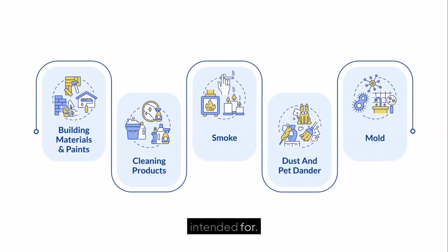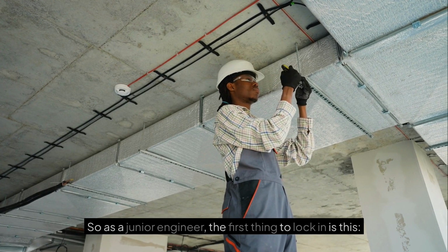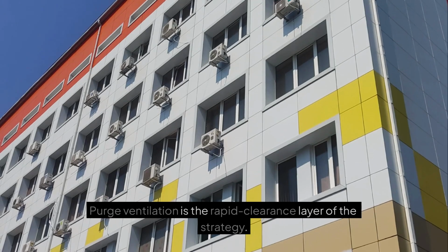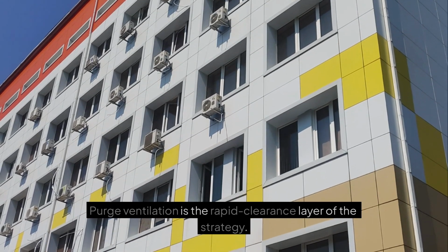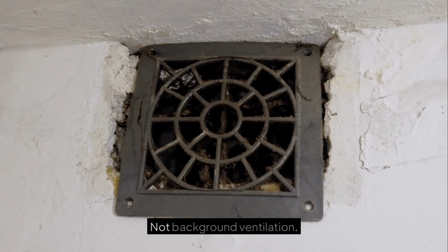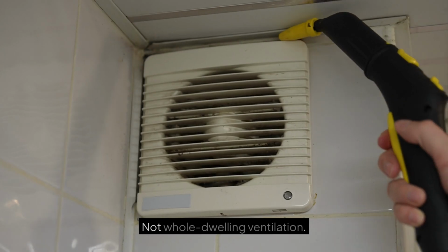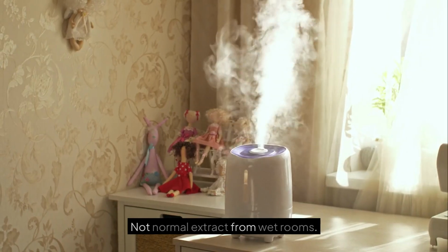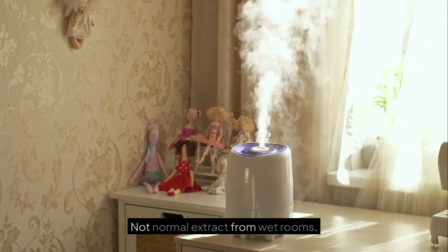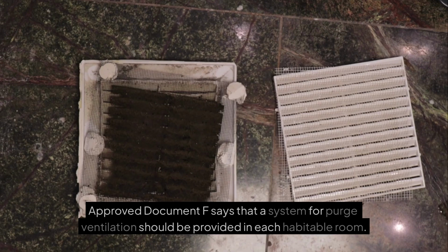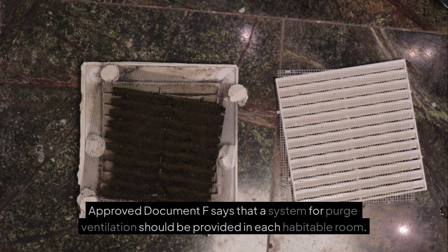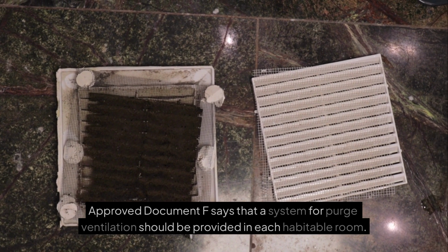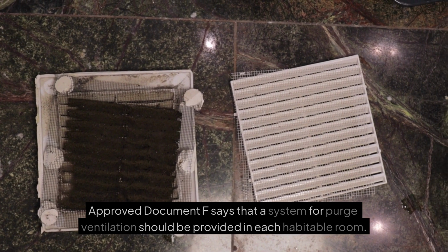So as a junior engineer, the first thing to lock in is this. Purge ventilation is the rapid clearance layer of the strategy. Not background ventilation, not whole dwelling ventilation, not normal extract from wet rooms. Rapid clearance. Approved Document F says that a system for purge ventilation should be provided in each habitable room.